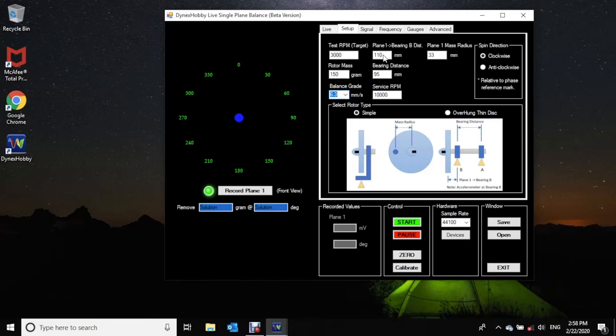The other items here are the plane 1 to bearing B distance, the bearing distance, and the plane 1 mass radius. I'll just talk about the plane 1 to bearing B distance. That's not really required for this type of setup, and the bearing distance is also not required for this type of setup, so we just leave them as they are. The service RPM is the maximum speed at which the EDF is expected to run. In my case, I'm just going to use an arbitrary value here of about 25,000 RPM.